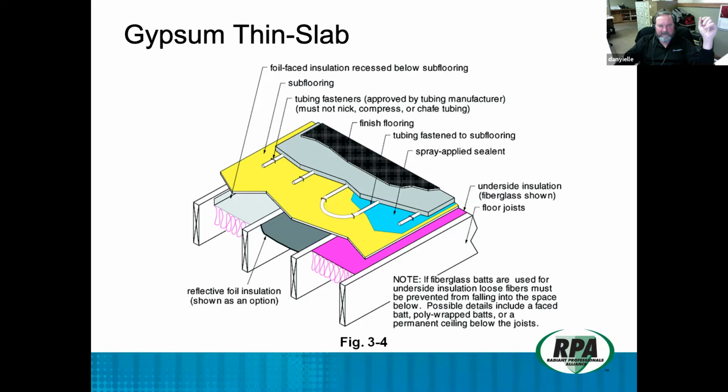It's actually a sheet of plastic that you put down onto the floor because the concrete has a higher coefficient of expansion. The gypcrete always remains somewhat liquidous because of the amount of sand that's in there. Whereas the lightweight concrete is going to get hard. It has a high coefficient of expansion, and if it bonds to the actual plywood subfloor itself, it will turn itself into a jigsaw puzzle. You will have cracks everywhere, and you don't want that.